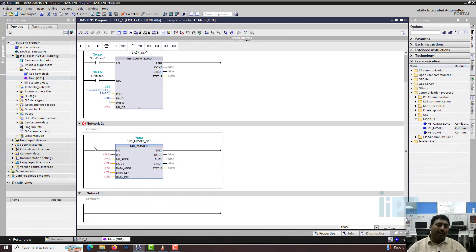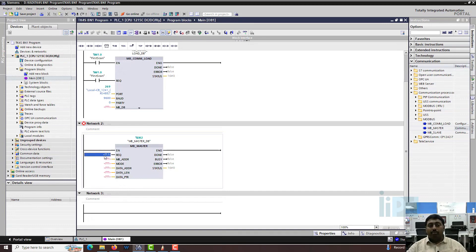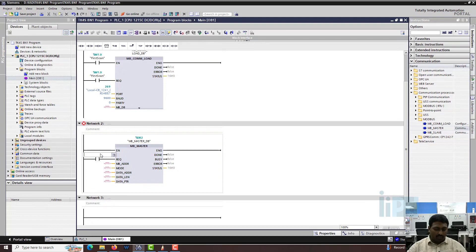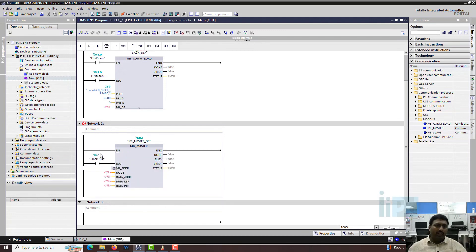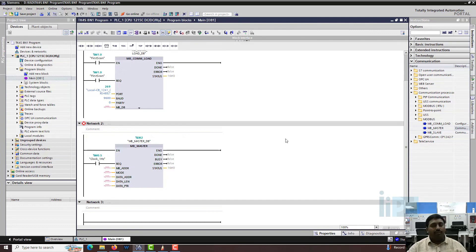On the MB_MASTER block, you have enable and request inputs. We can leave the enable as-is - no separate enable command is needed. For the request, we need a cyclic request to get data continuously, so I will give the clock cycle M0.5, which is a 1 Hz clock - half a second on and half a second off. You can increase the speed if needed, but half a second should be fine.